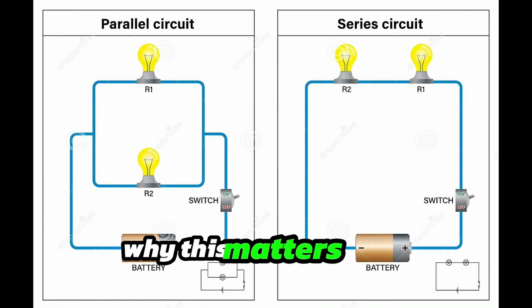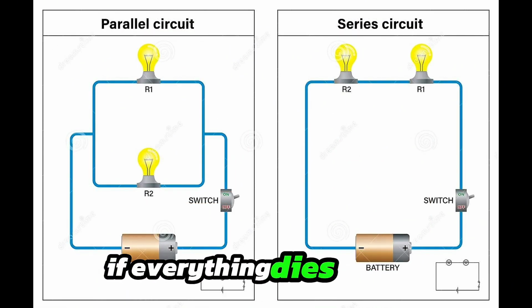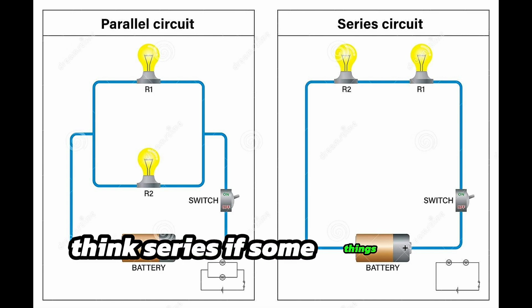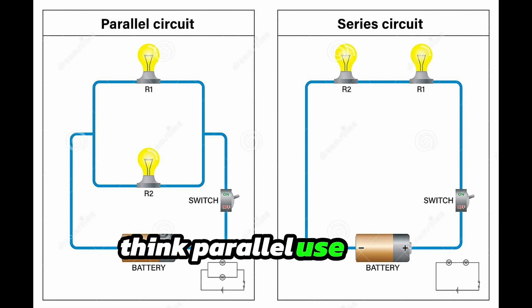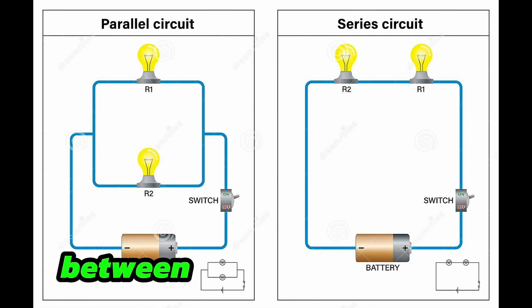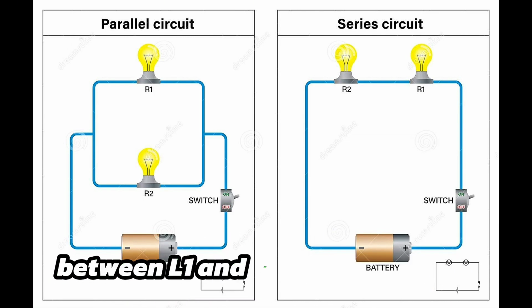Why this matters? When troubleshooting, if everything dies at once, think series. If some things still work, think parallel.